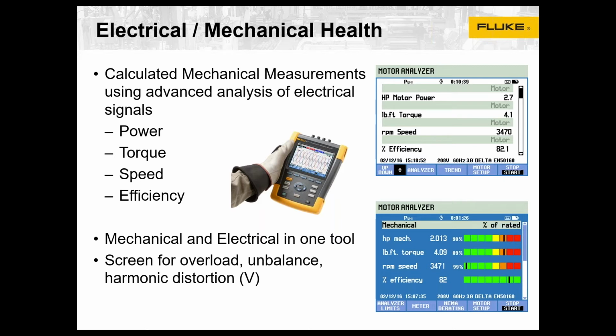There are tools now, handheld tools, that not only can make electrical power measurements, but they can also derive torque and speed from the electrical measurement to be able to determine mechanical efficiency, and then to examine things that might affect motor life, for example, looking for mechanical overloads, unbalance, distortion, all things that can cause additional heating and shorten the life of the motor.